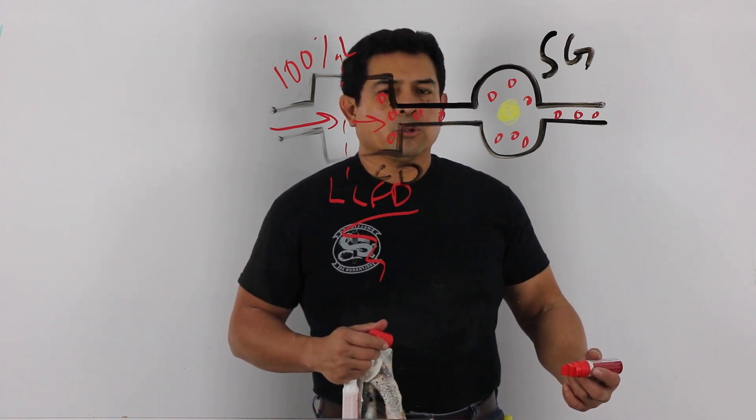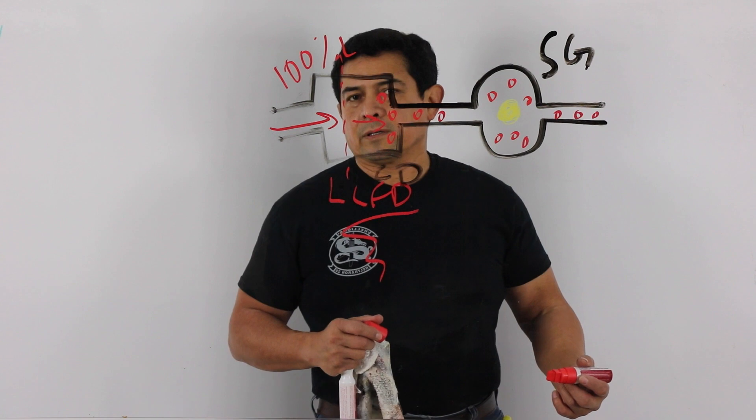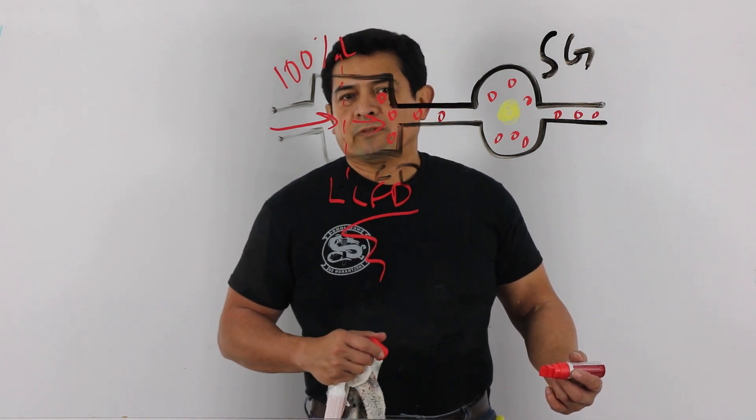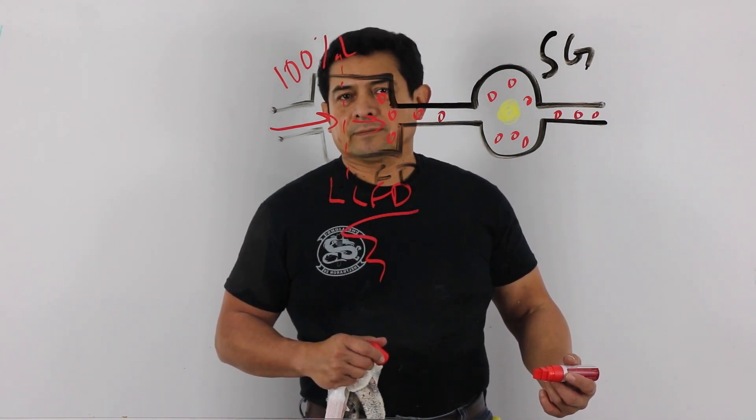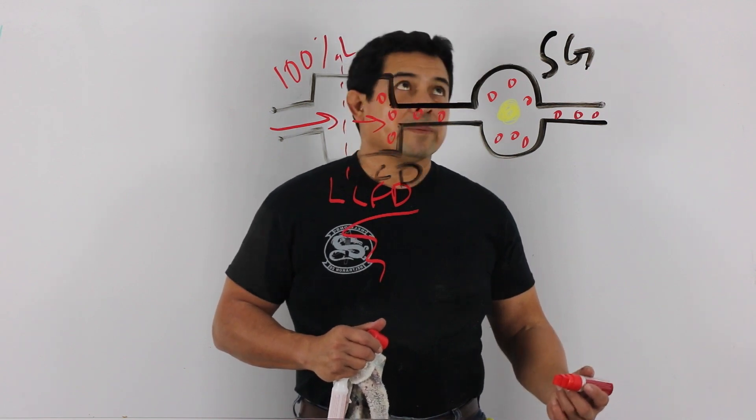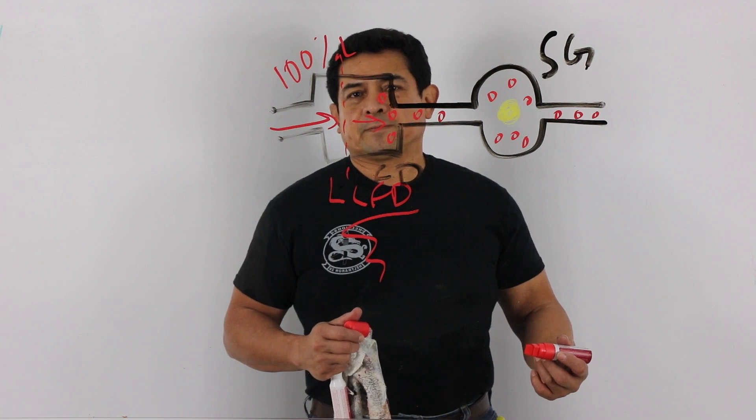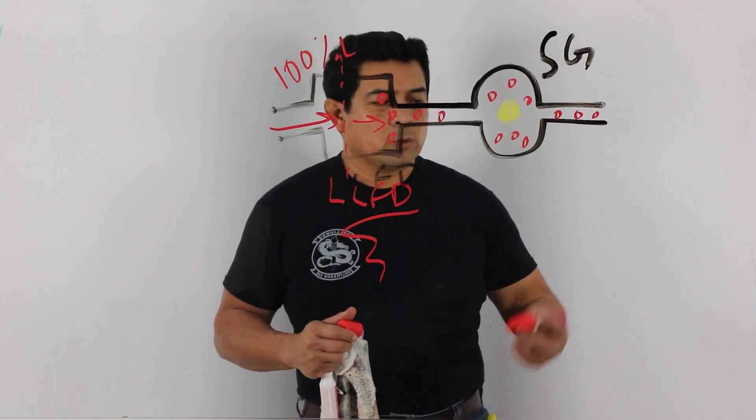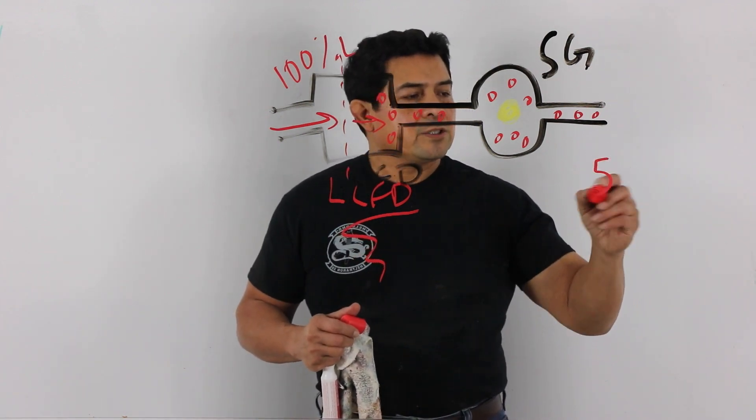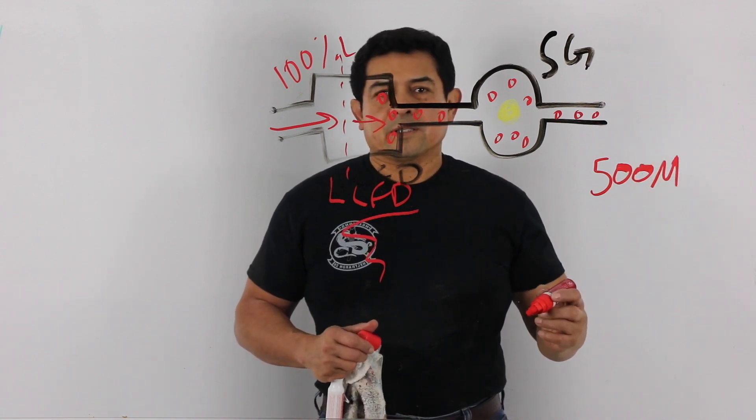How long? Some mechanics say 10 minutes, 20 minutes, 30 minutes. It depends. Well, guess what? The time doesn't matter. It doesn't matter how long you pull it for. What's important is that you get down to 500 microns.